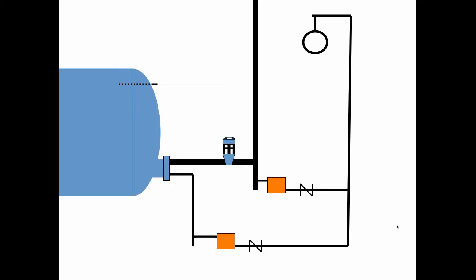Let's make this a little bit more interesting. Here we're heating domestic hot water in this big tank and we're going to have what's called a bayonet heater sticking inside of the tank. And we're reversing it here because now the water is inside the tank and the steam is inside the coil. So the bayonet heater is just this big trombone-like device that goes in there and steam's inside of it and it turns around to condensate, comes back by gravity and it's flowing down through a trap.